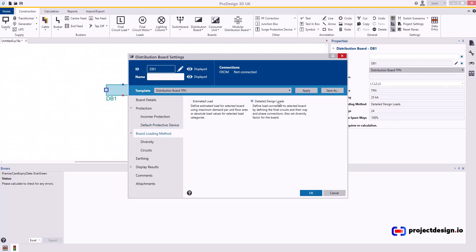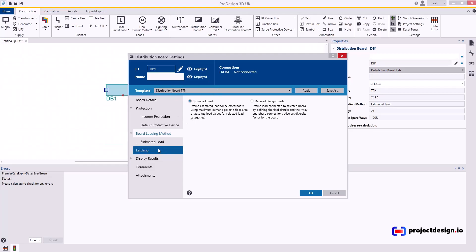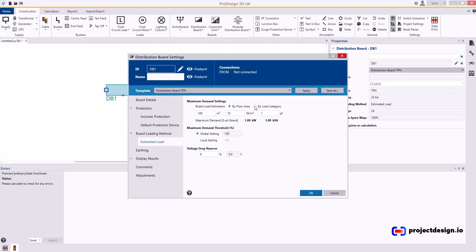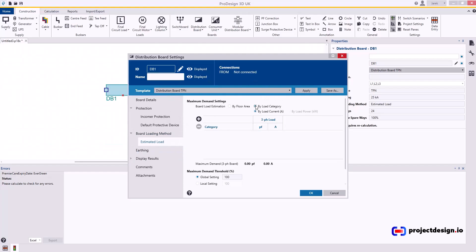Board loading method will be detailed design load, but you can also use estimated load. When I build my system, I may have a typical floor built in detail with final circuits, and then I will use the load from level 1 and apply it into level 2 as estimated load. So you select estimated load, typically used by load category. Click that.